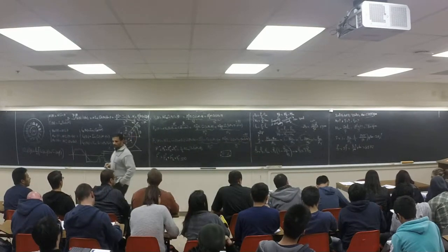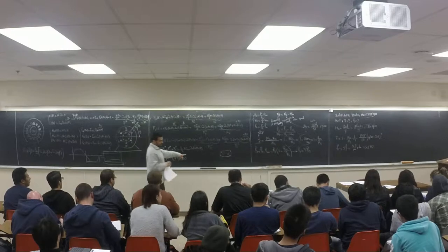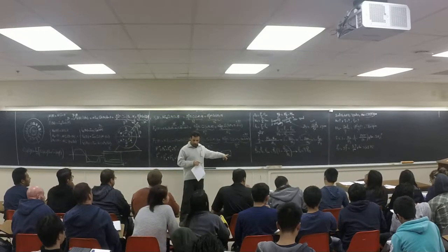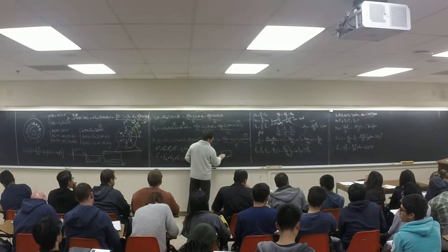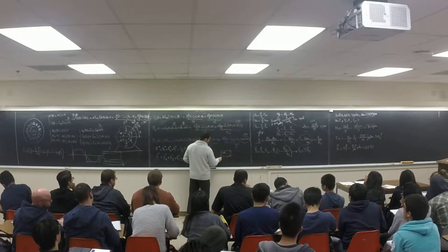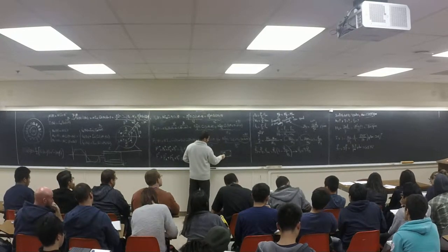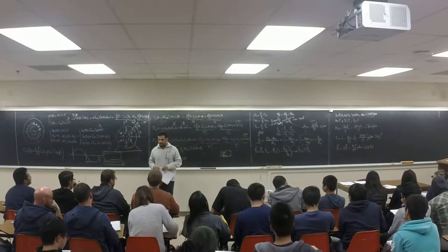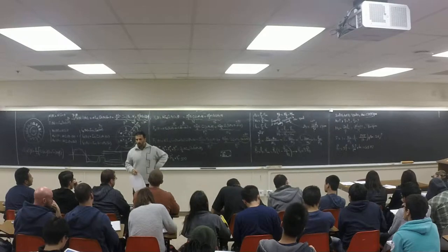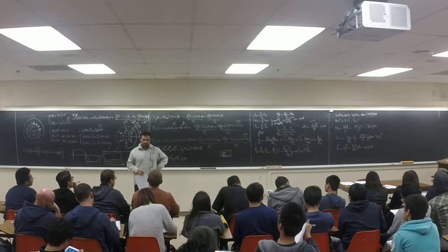Lots of times, the nameplate of a machine won't tell you how many poles the machine has. I'm going to ask you this question. We have a machine here; the nameplate says 208 volts, 60 hertz, 1755 RPM. They don't put the number of poles. How many poles is this machine?